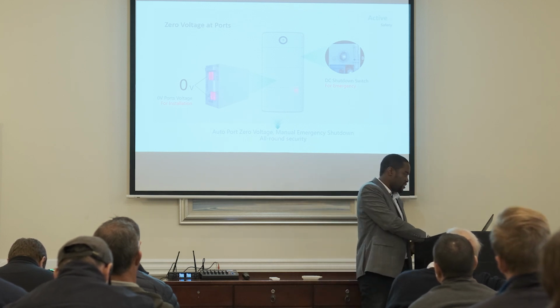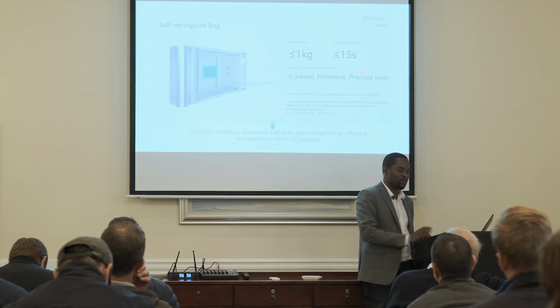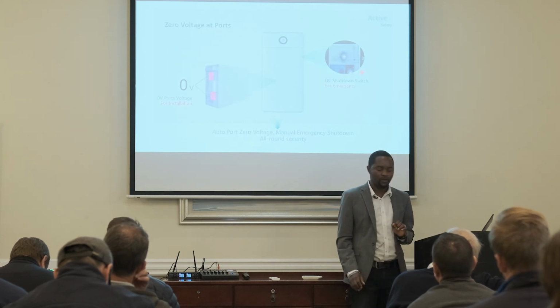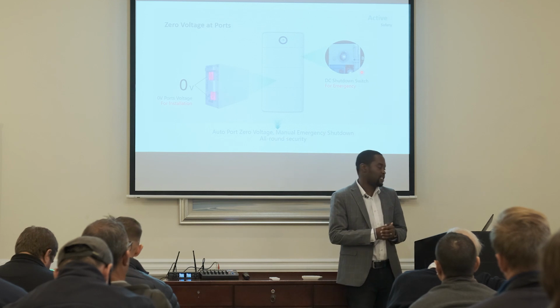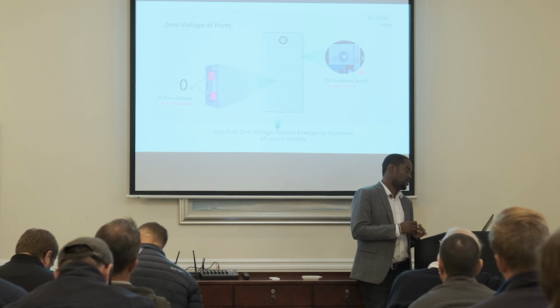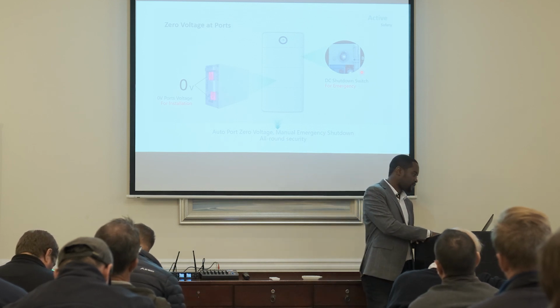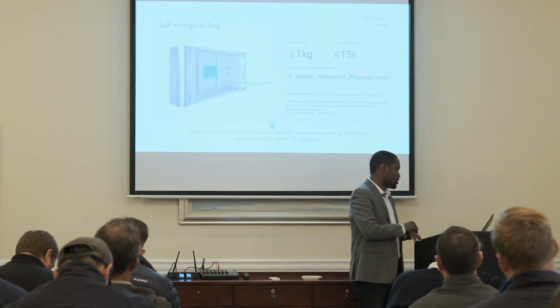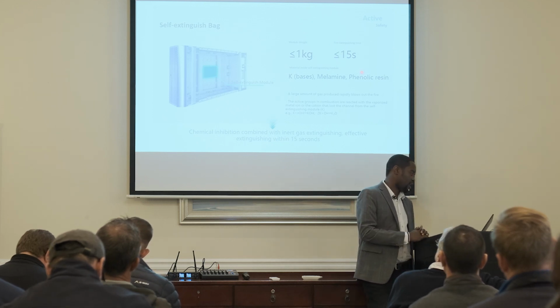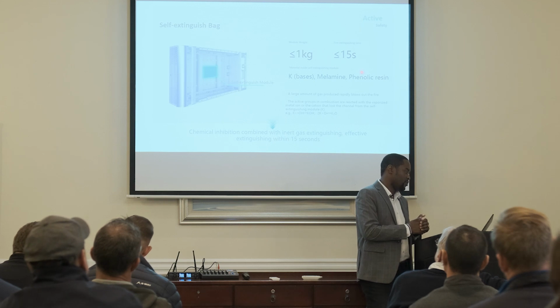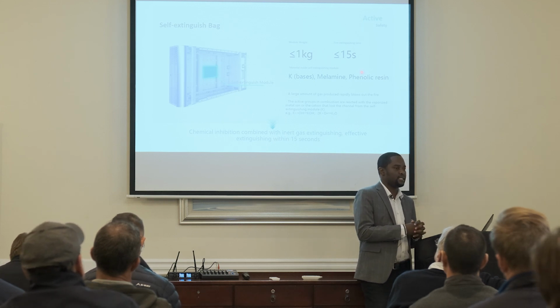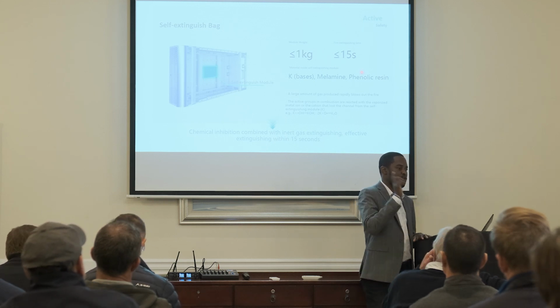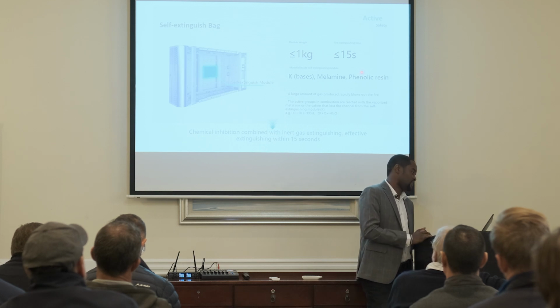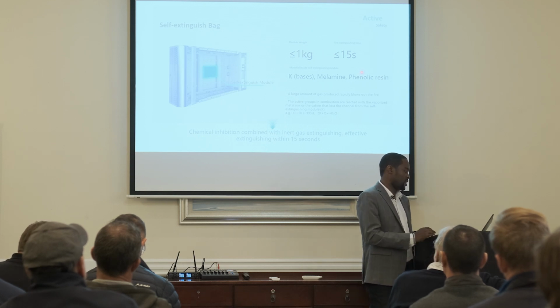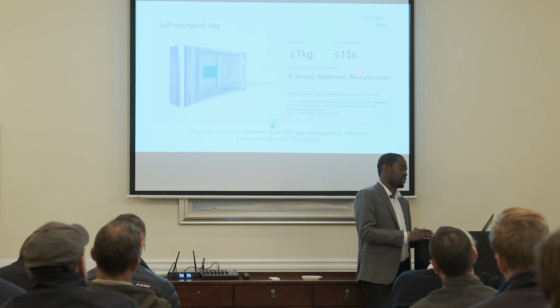You also have this DC switch. It's an emergency switch. So at any given time, if you push in that button, it stops the whole system. There's also extra protection. Then the fire packs, the self-extinguish module, Raf has touched on this. When you're measuring the temperature, if it gets to 90 degrees Celsius, then that automatically is triggered. Then it produces a gas that will extinguish any fire and damage the batteries.